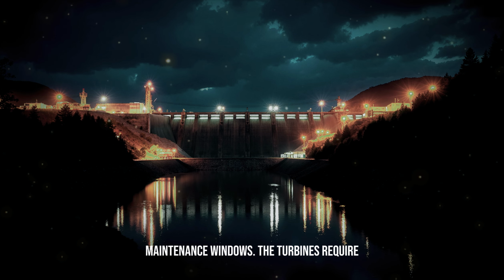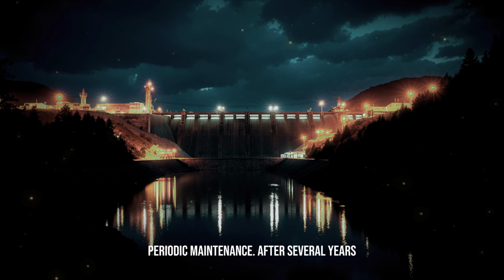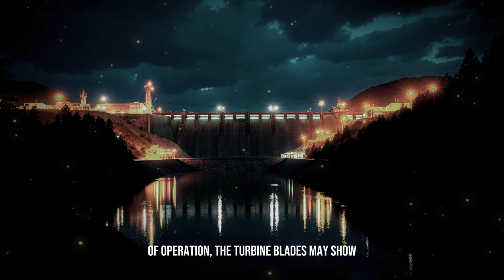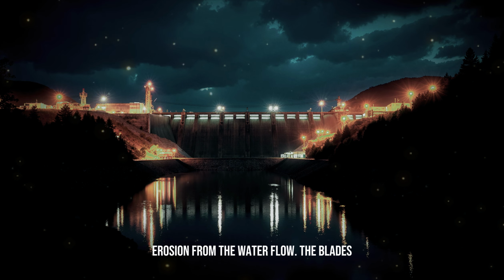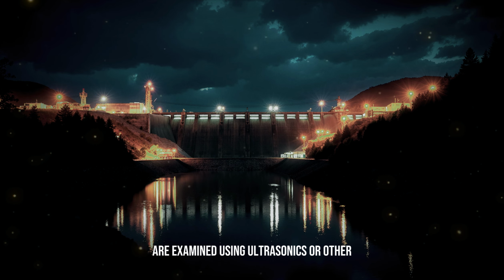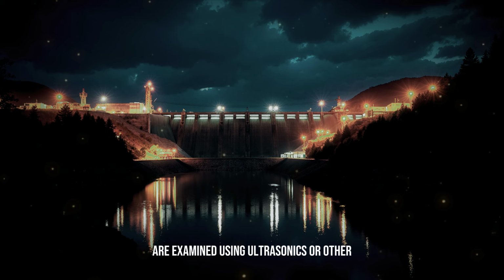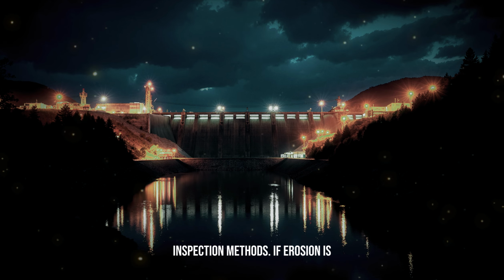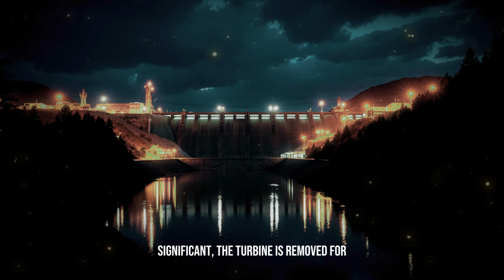The turbines require periodic maintenance. After several years of operation, the turbine blades may show erosion from the water flow. The blades are examined using ultrasonics or other inspection methods. If erosion is significant, the turbine is removed for refurbishment.